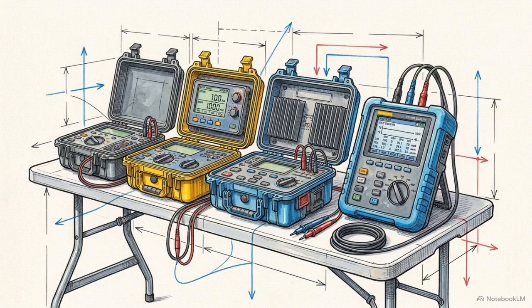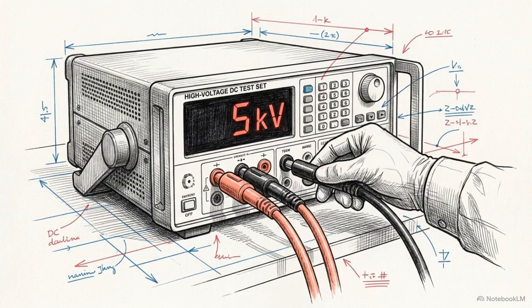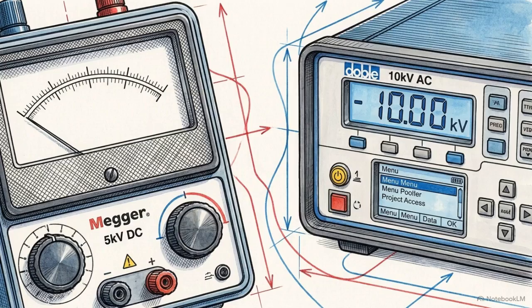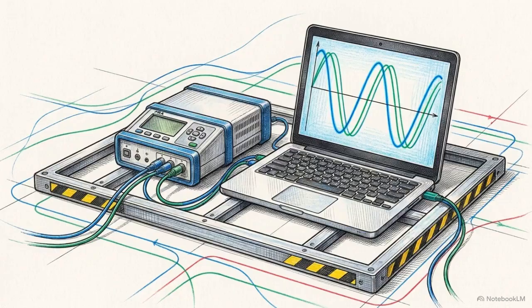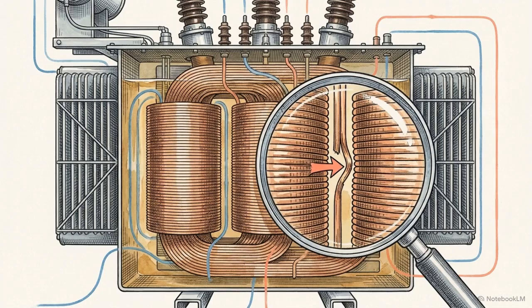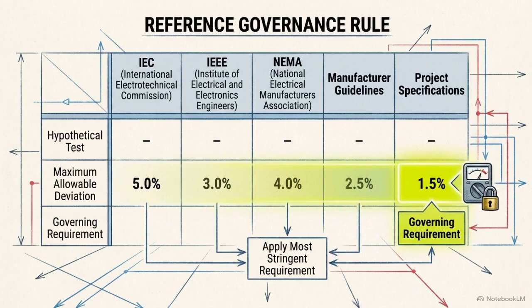Generating that data requires highly specialized instrumentation. To stress the insulation boundaries, technicians deploy high-voltage DC and AC testers, most notably the 5 kV Megger and the 10 kV Doble test set. To evaluate the internal windings and core, they use low-resistance microohmmeters and frequency response analyzers, capable of detecting millimeter-scale mechanical shifts inside the tank. Every measurement is evaluated against a strict regulatory hierarchy, referencing IEC, IEEE, and NEMA standards.